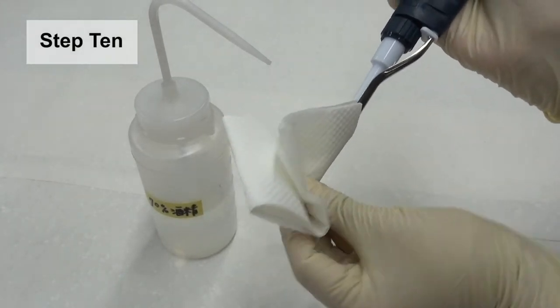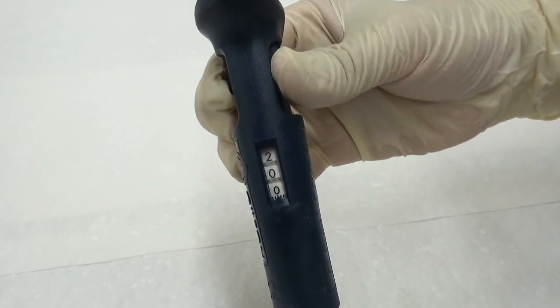Step 10: Clean the pipette immediately after use. Set the volume adjustment dial to its upper limit. This shall protect the internal parts from elastic fatigue.